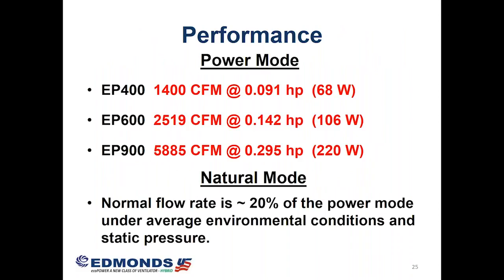On the performance side of things, the key to this hybrid technology is its low power in operating mode, while extracting energy from the wind and providing free ventilation in the natural mode. In operating mode, power consumption ranges from 1/10 to 3/10 of a horsepower. With 20-mile-an-hour winds, you will reduce the power consumption by approximately 6%. At 33 miles an hour, you will save up to 17%.